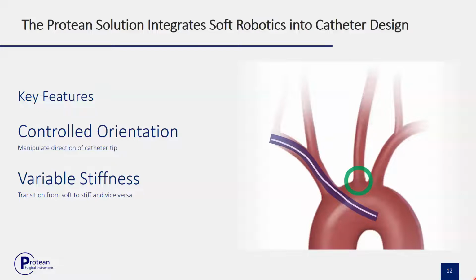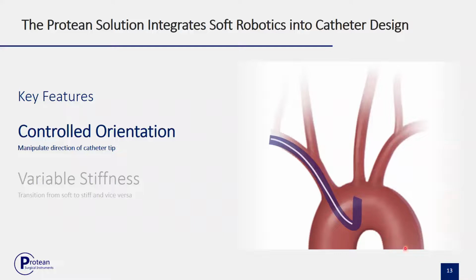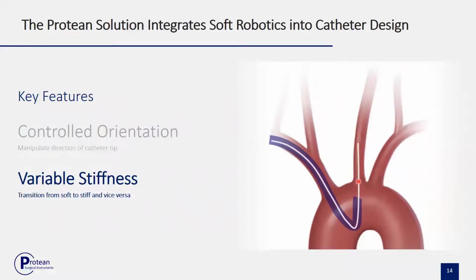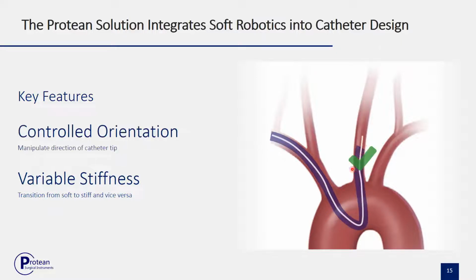Our proprietary catheter technology utilizes soft robotic principles to allow the proceduralist to manipulate segments of the catheter within the body. This will improve catheter navigation for radial artery access. The Protean catheter will provide controlled orientation circumventing the need to form the Simmons loop we showed earlier. Once pointed in the correct direction, the proceduralist can modulate the catheter stiffness to facilitate passage of the guide wire without dislodging the catheter. With the guide wire securely in the target branch, the catheter can be softened and tracked up the guide wire, resulting in successful access.